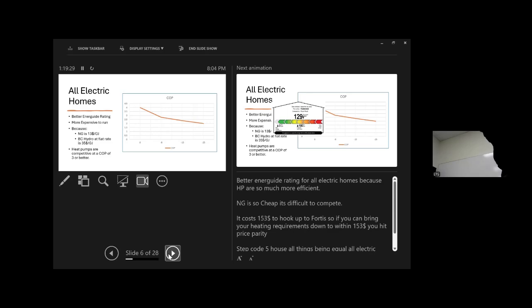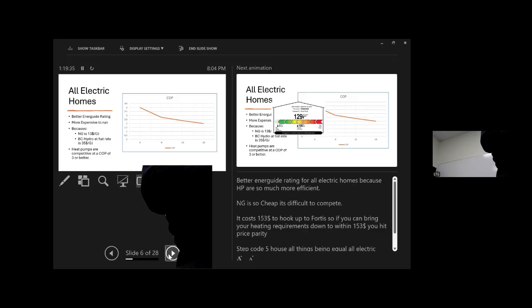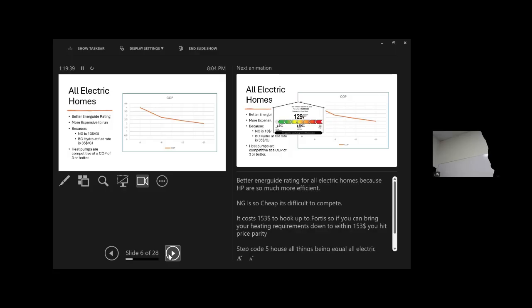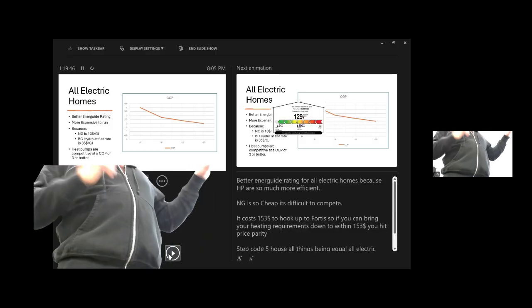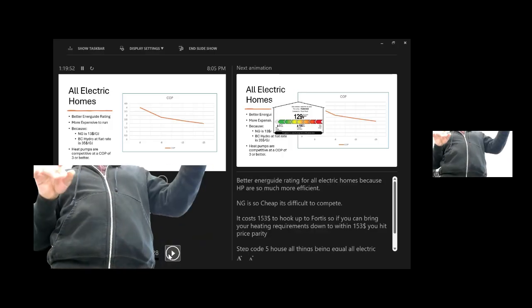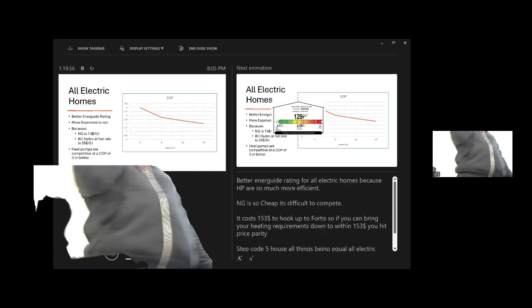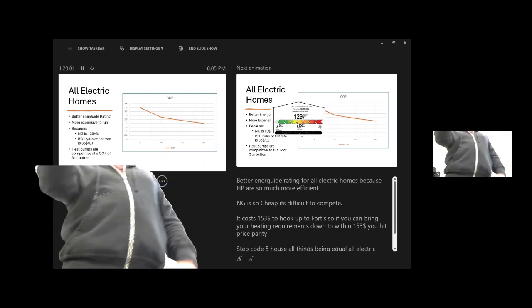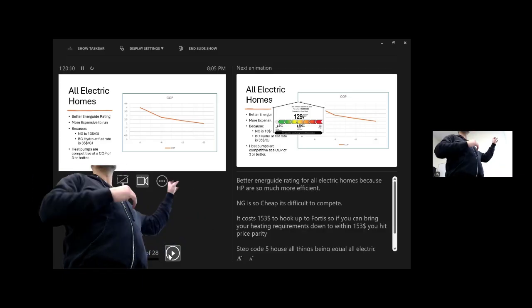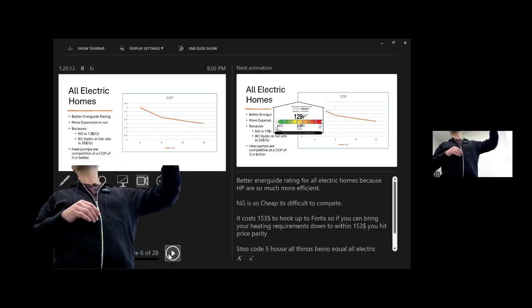And I was going to bring, what is it, how much energy they put out. So BTUs, so capacity, that's what it is. With a heat pump, for this one, sort of the best of the best, you'll probably get 2 units of heat per unit of electricity. But the total capacity has reduced. Yes, your 2-ton heat pump is down to less than 1 ton. That's where the sizing becomes really important. Like my 2-ton, when it's at minus 10, is only going to be putting out 1 ton. And as it gets colder, your capacity is going to go down.